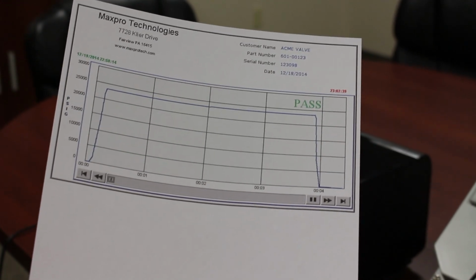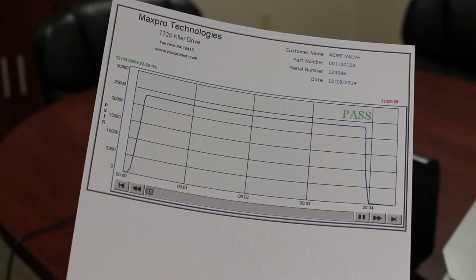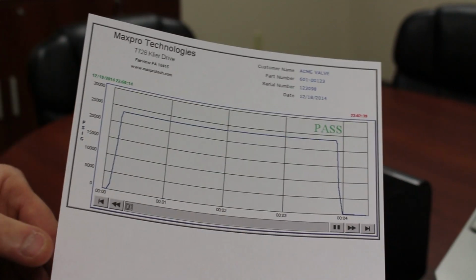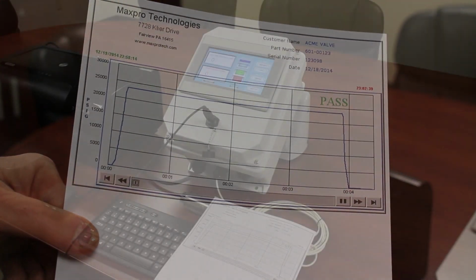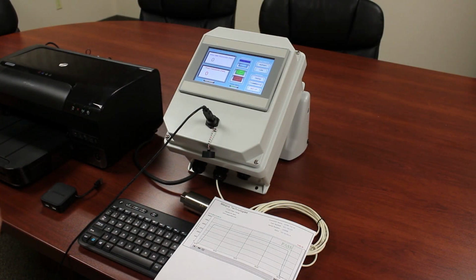Nice thing about this is you don't have to manipulate any data in an Excel file or anything like that to create a test report. All you do is hit the printer button and it gives you a test report. You also have the option of saving the data. Even after you've printed it, you can still save it to a USB drive to take to your computer and save that electronically. The logger is a very reliable way to record your pressure test. You can store them electronically and print them out, have a hard copy of your test. Much better than using a chart recorder where all you have is a paper copy of the test.